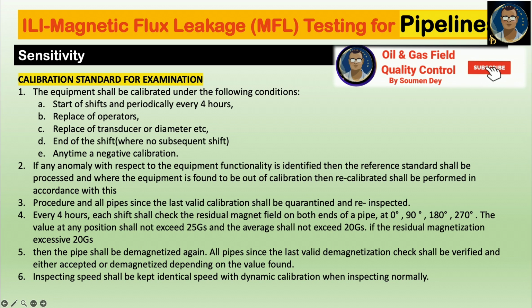Calibration standard for examination. So the equipment shall be calibrated under the following conditions. Start of shift, periodically every 4 hours. So we need to do calibration when we start the work or start the shift, and then every 4 hours we need to again repeat the calibration to make sure that the machine has no issues.